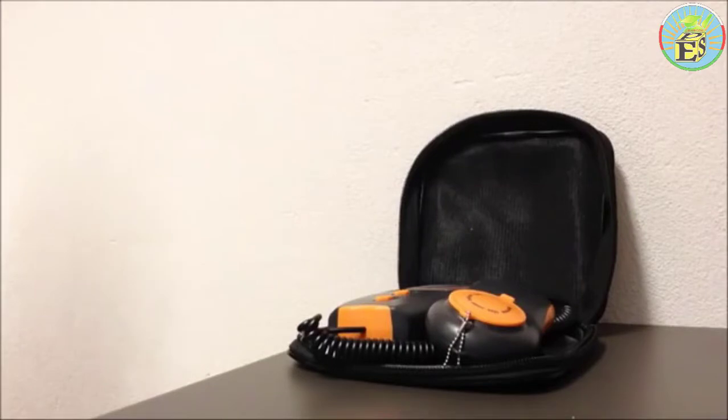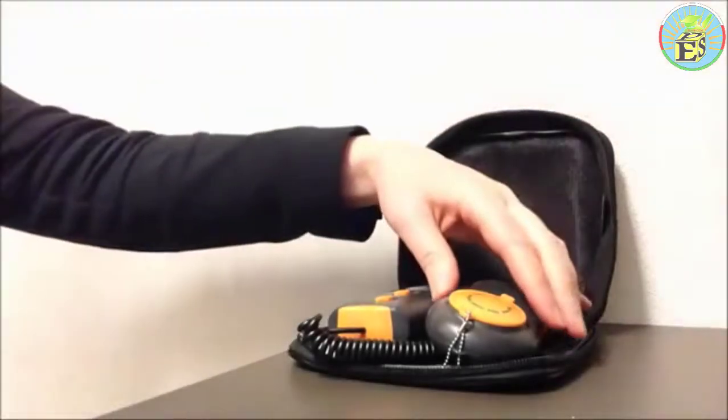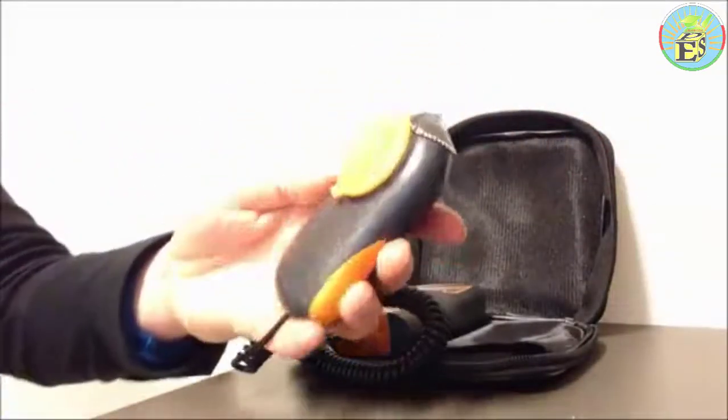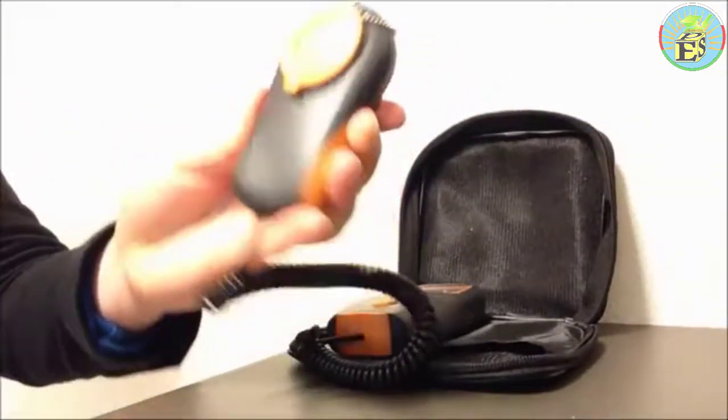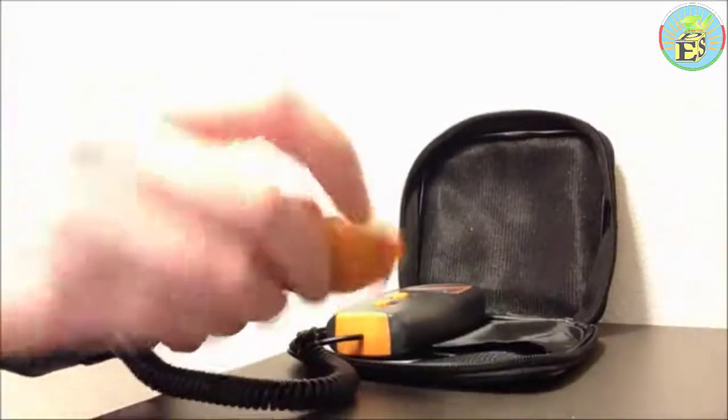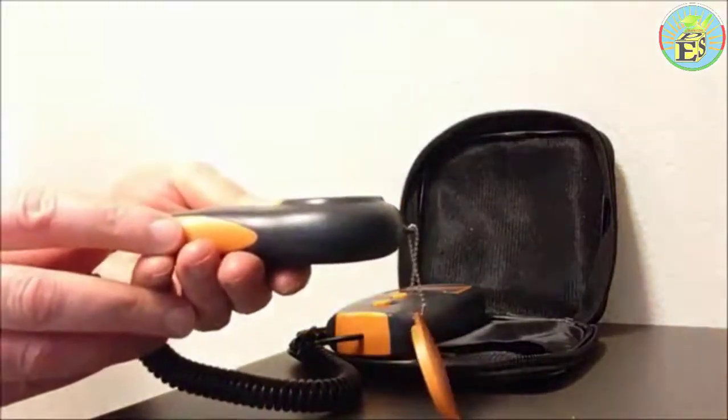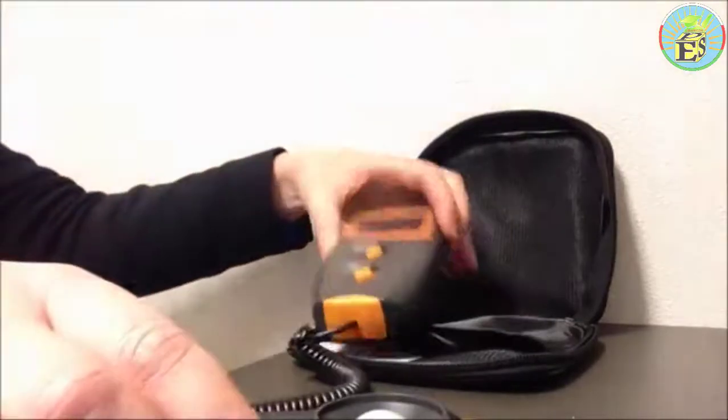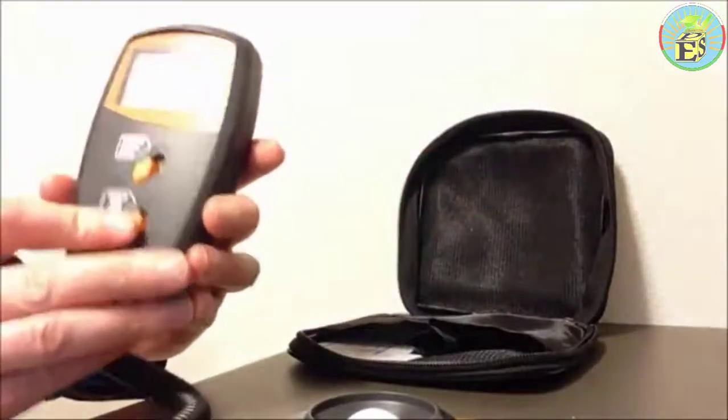The Australian and New Zealand standards set out the required lux levels for working areas. For example, regular office spaces require lux levels of about 320 lux compared to a storeroom or a loading bay, which would require about 80 lux. In order to using this tool, may find lighting levels are too high for a certain space and may recommend reducing lighting levels. This lux meter is very simple to use.